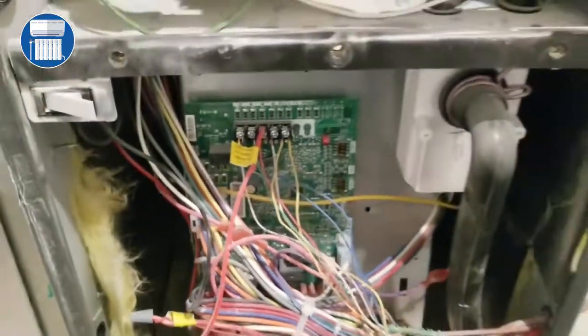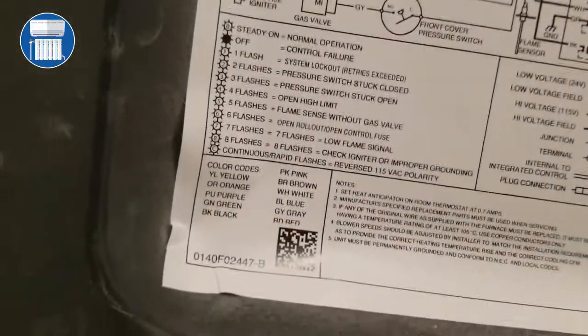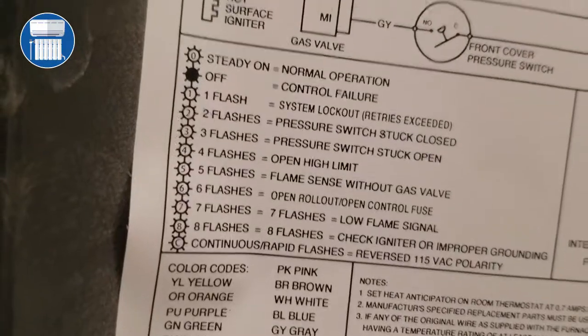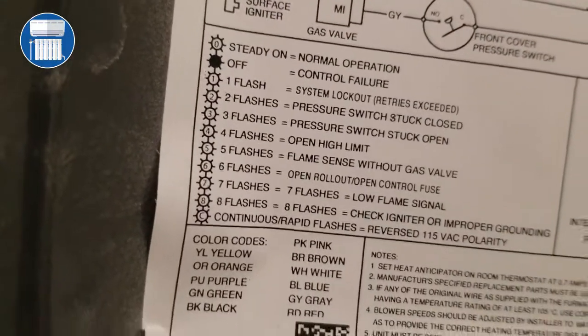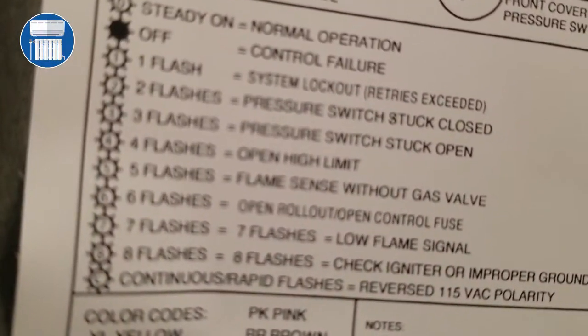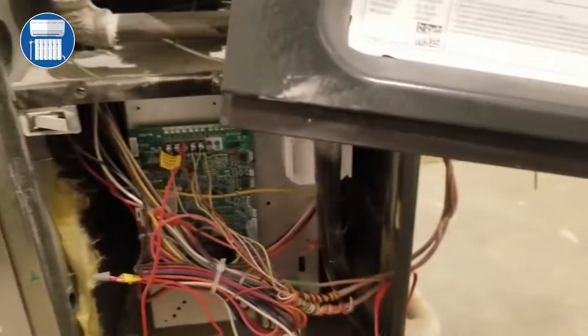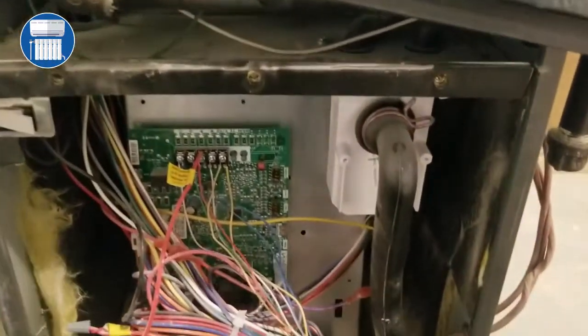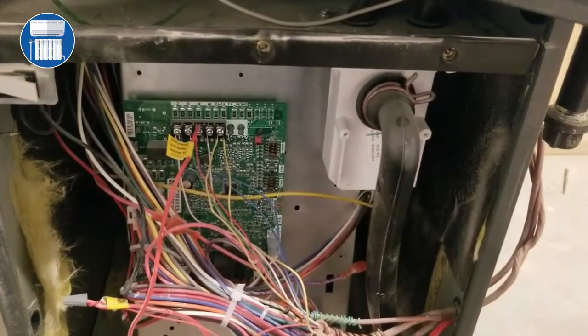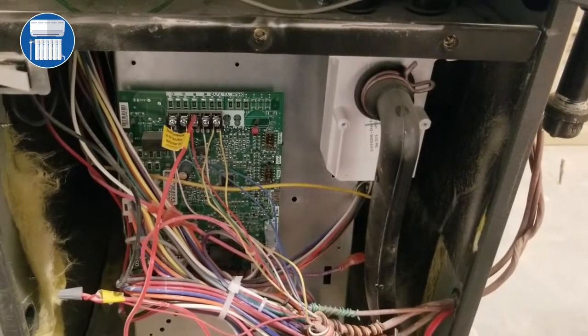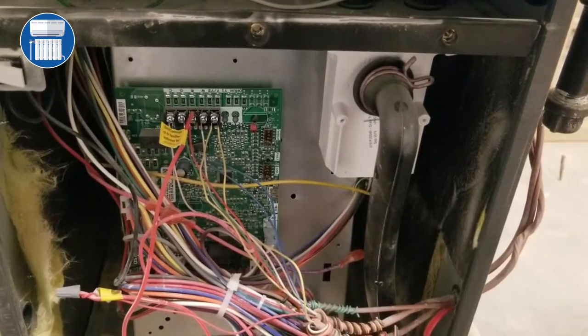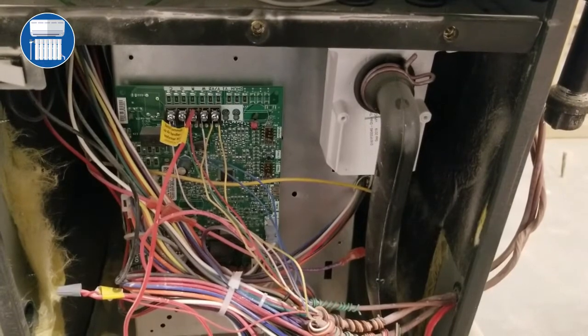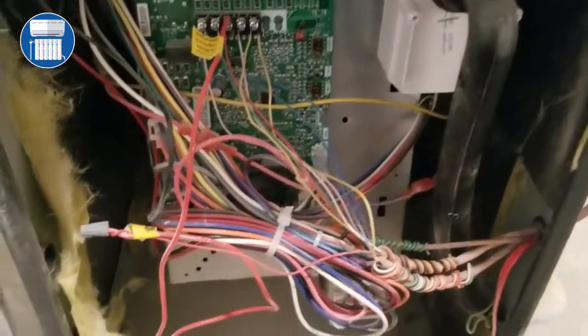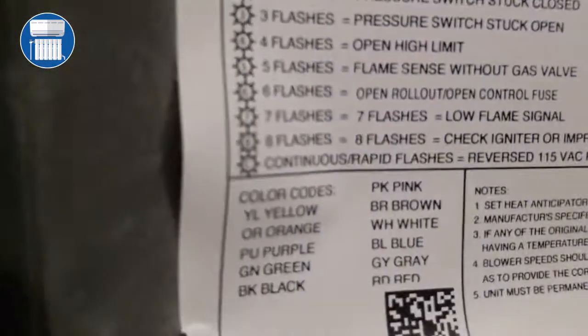I want to concentrate on the back of this board, this plate, because it tells you all the necessary codes. All you have to do is look at your furnace, look at the codes, and it will tell you what the problem is. I'm going to go through some of the major codes that you will see. It says pressure switch stuck open. On this furnace, which is a Goodman, we have 3 flashes for pressure switch stuck open.